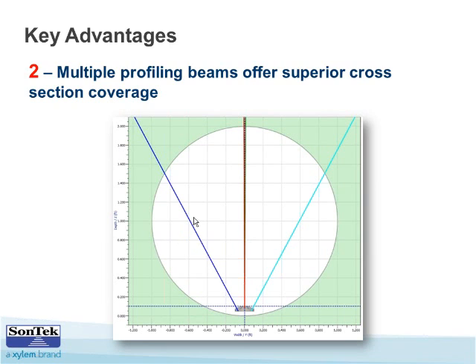Say the water level was only halfway—the instrument would not use information beyond what the vertical beam or the pressure sensor was telling it. So if the pipe was half full and the rest totally empty, the instrument would know that, cut those beams off, and still make a well-informed flow calculation.